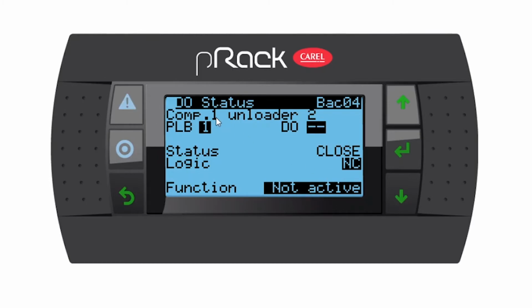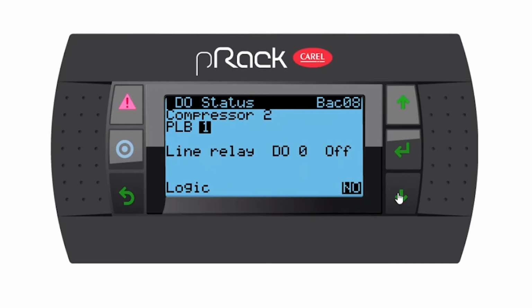If we go down, compressor 1 unloader 2, and this is going to be 8, because that's an SSR output. I'm going to leave the logic as normally closed. If we go down, compressor 1 unloader 3, and this I'm going to make, as per the notes, number 12. Perfect. Normally closed. Okay, if we go down, compressor 1 fan cooling. Do you have a cooling fan for that compressor? If you do, you have to assign it. Mine don't, so I'm going to leave it as no and go down.